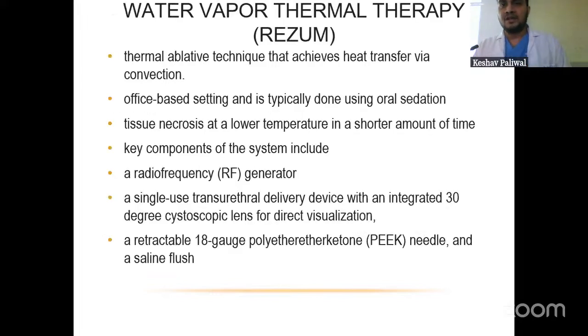The water vapor thermal therapy, popularly called Rezum, is a thermal ablative technique that achieves heat transfer via convection, in an office-based setting, and is typically done using oral sedation. Tissue necrosis occurs at a lower temperature in a shorter amount of time. Key components of the system include a radio frequency generator, a single-use transurethral delivery device with an integrated 30-degree cystoscopic lens for direct visualization, a retractable 18 gauge polyether ether ketone needle, and a saline flush.